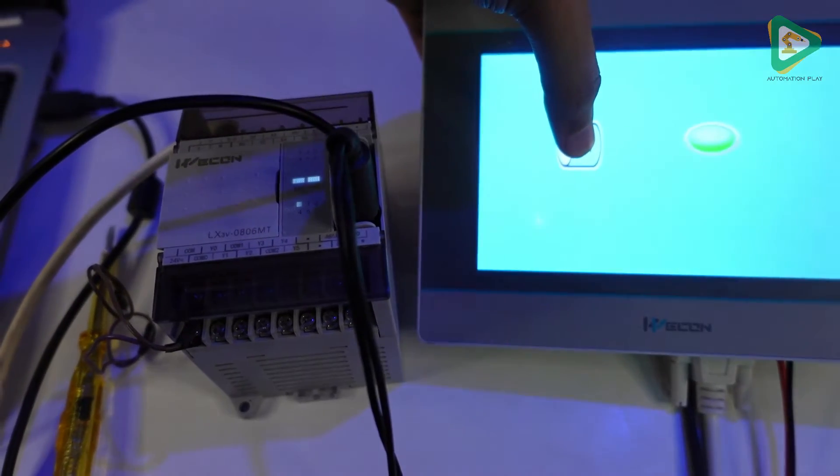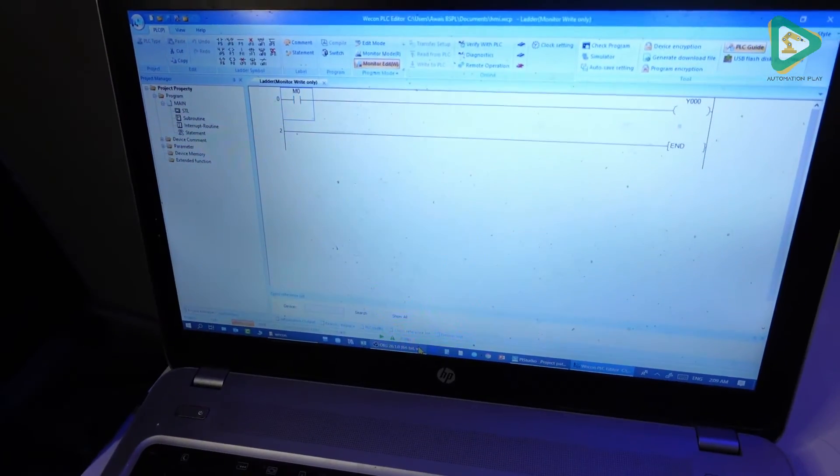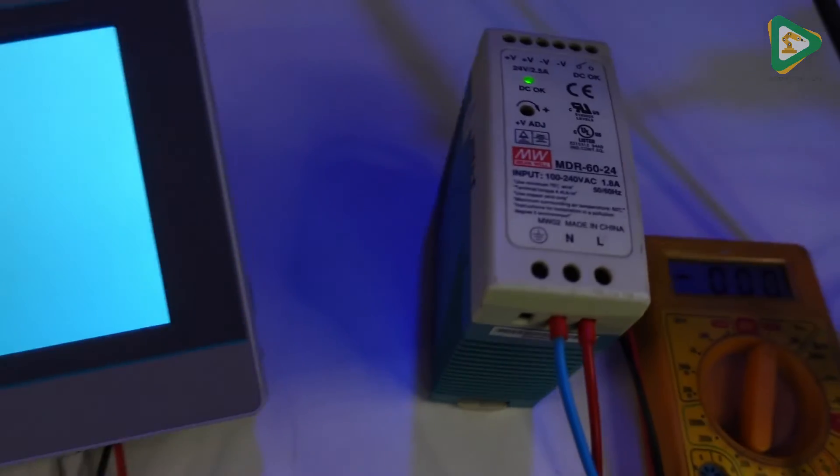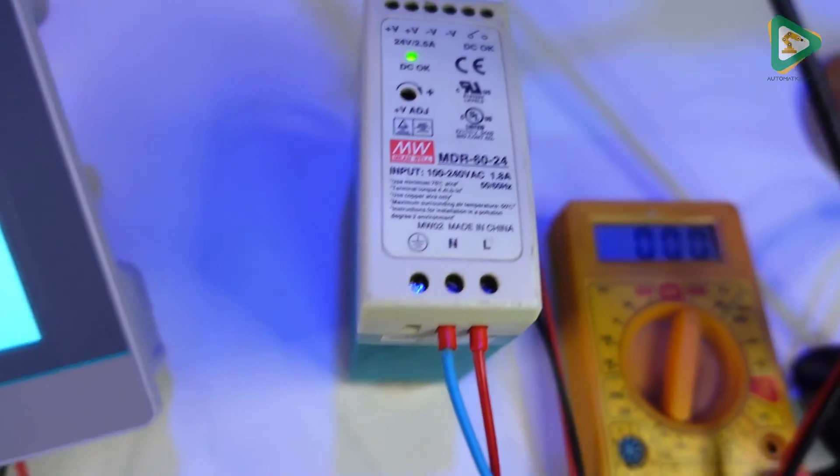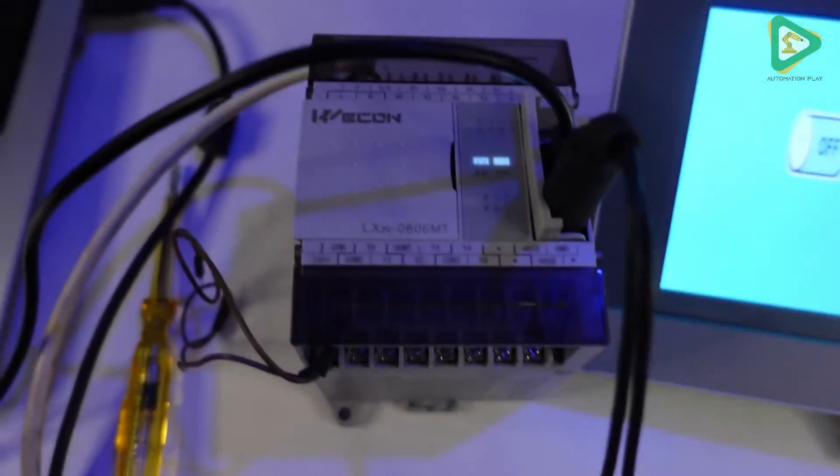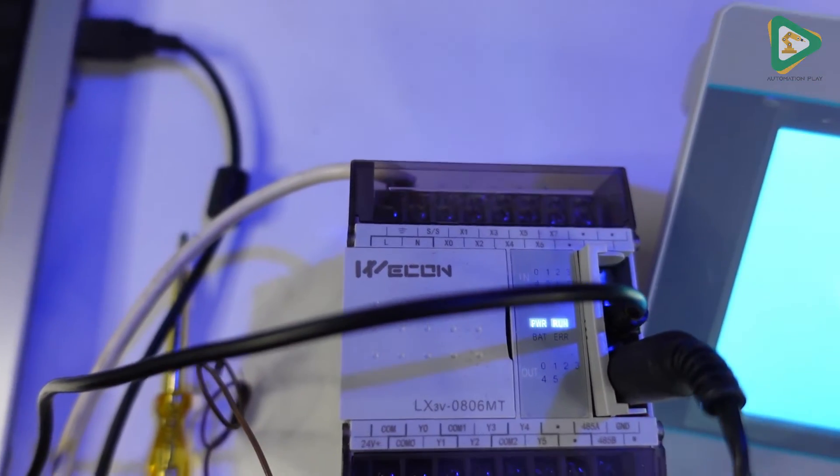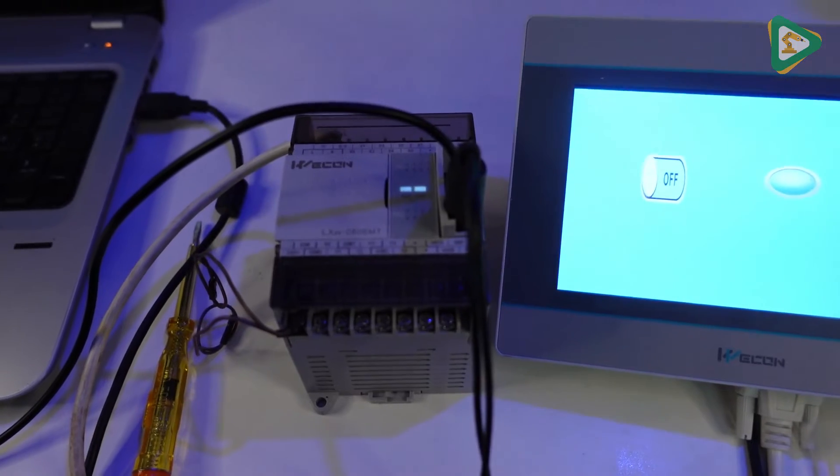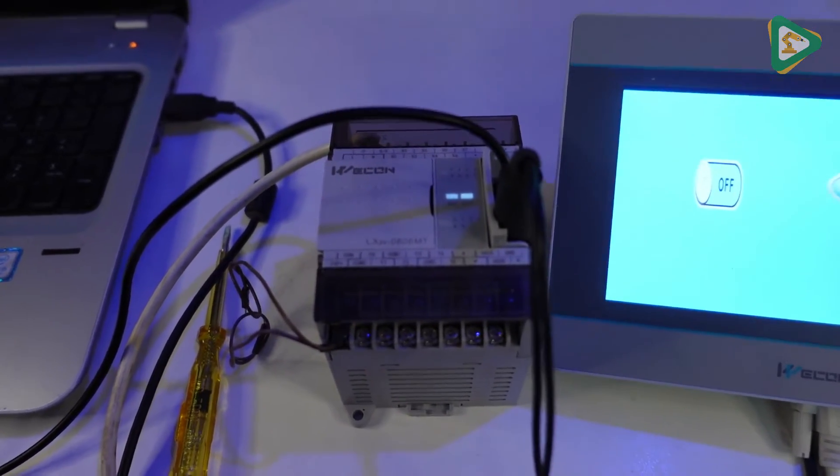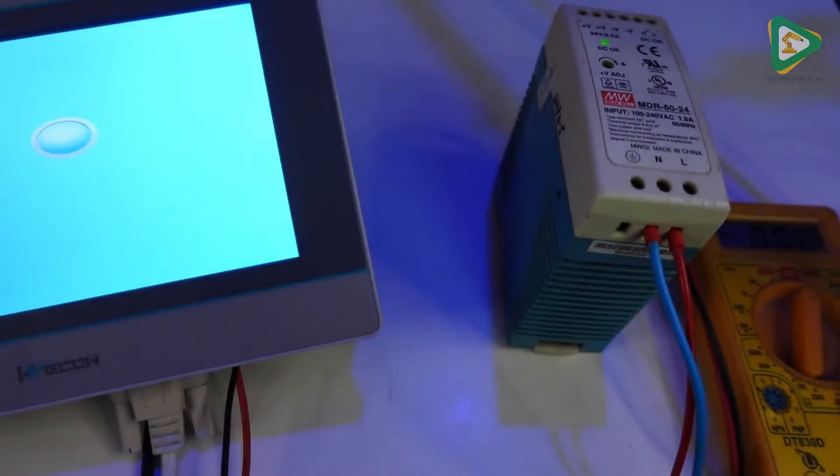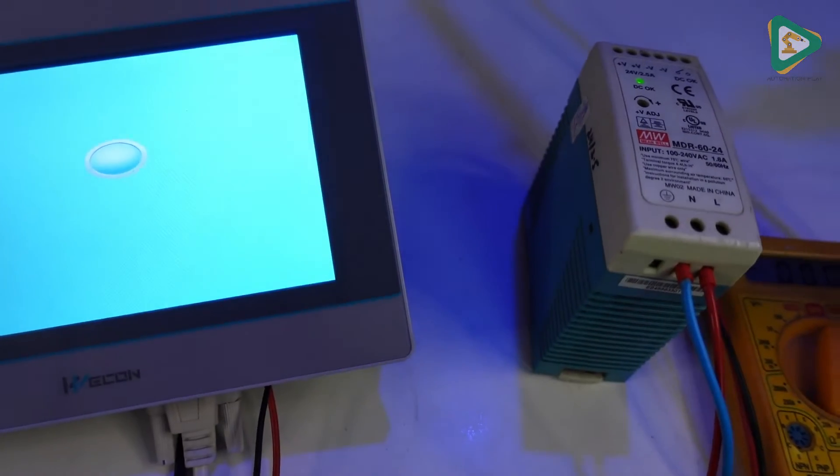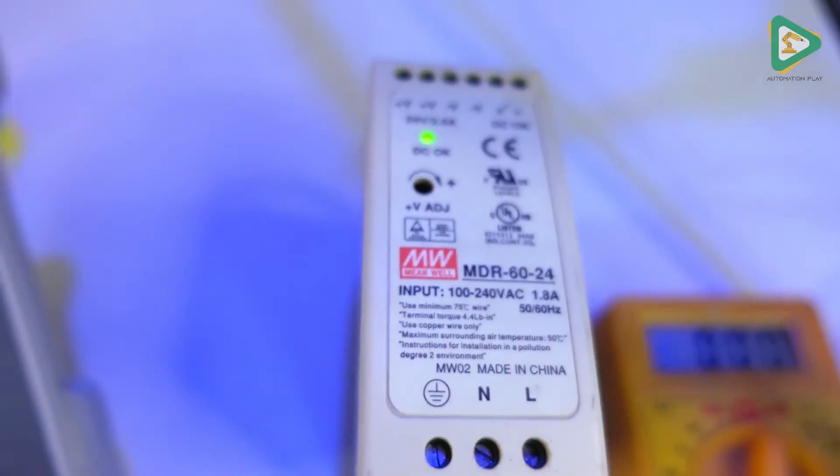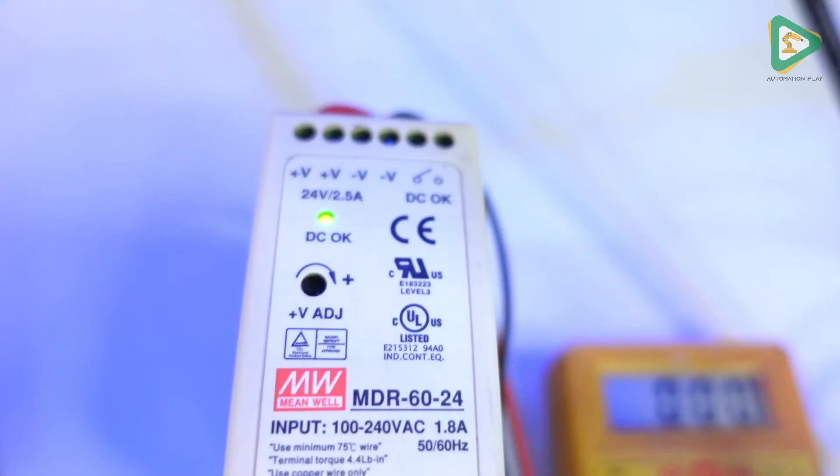And the light is turning on here as well on the PLC, and you can see on the laptop as well. Just one more thing, I'm using this power supply over here, 24 volt power supply, which is connected to my HMI. My PLC is getting 220 volt directly, which we have already covered in the previous lesson. PLCs can be powered using 220 volt as well, that depends upon the model. But 99.9% of the time, HMI is powered up using 24 volt supply. The HMI takes 0.5 amperes and my power supply is around, I believe, 2.5 amperes.